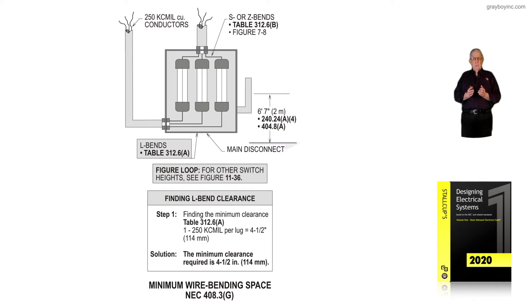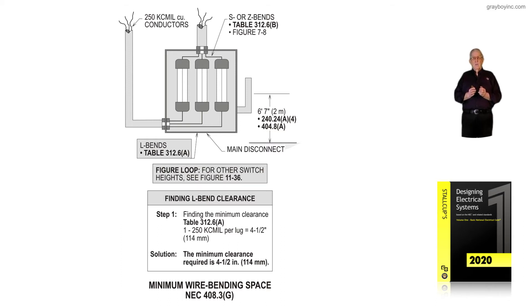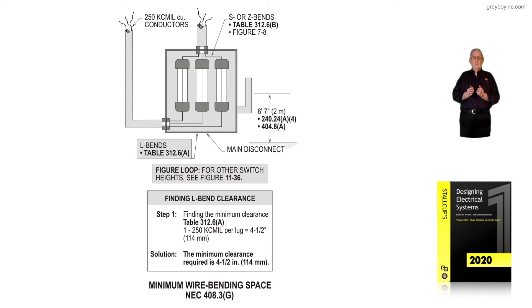The L-bend is sized from table 312.6A — not table 312.6B. Notice we have a figure loop for other switch heights; we can go to 11-36, chapter 11.